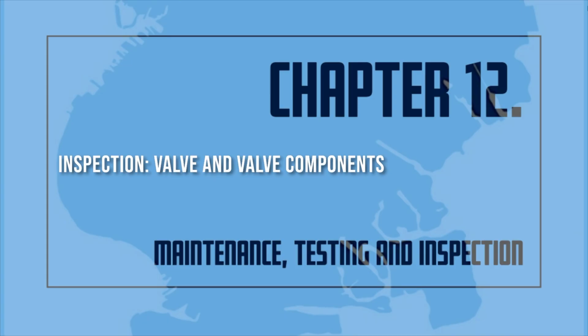Pressure reducing and relief valves. Fire pumps. Casing relief valves. All circulation relief valves shall be inspected weekly to verify that water flows through the valve when the fire pump is operating at shutoff pressure or churn to prevent the pump from overheating. Pressure relief valves shall be inspected weekly to verify that the pressure downstream of the relief valve fittings in the fire pump discharge piping does not exceed the pressure for which the system components are rated. Sprinkler systems. All valves shall be inspected quarterly to verify that the valves in the open position are not leaking and are in good condition, with hand wheels installed and unbroken. Downstream pressures shall be maintained in accordance with the design criteria.